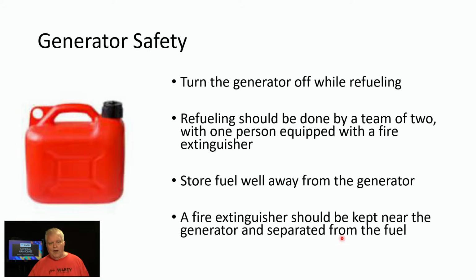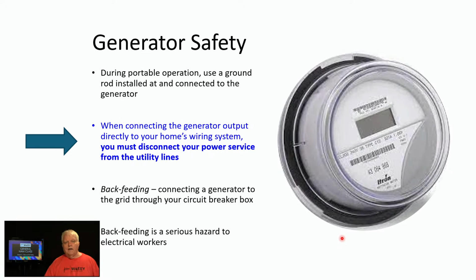Now, if you're going to be powering your house during an emergency condition, like we had Hurricane Helene here about a year ago, and a lot of folks were running generators, during operation you want to make sure that you disconnect from the power lines coming into your house. One way to do that is to break the seal on your meter and just yank the meter. It's in a socket. I don't know if you knew that. And you can yank it straight out. And that will give you a visible means of disconnection. You've disconnected your house from the rest of the lines that are going through your neighborhood. Then you can power your house with a generator.